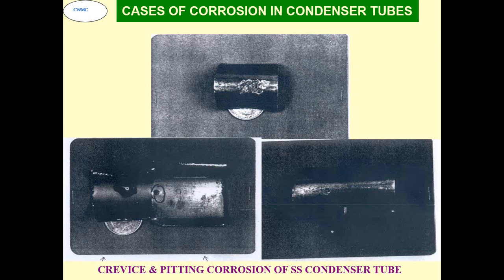These are the stainless steel condenser tubes which were transported through sea route, and either during transportation or during storage, seawater has ingressed into the system. From the portion where the ropes were tied, below that portion crevice corrosion took place and the tubes lost their thickness, and when they were hydro tested, almost 700 tubes failed during the hydro test. Of course, tubes were replaced by the vendor, but commissioning time of about 1 year was lost.